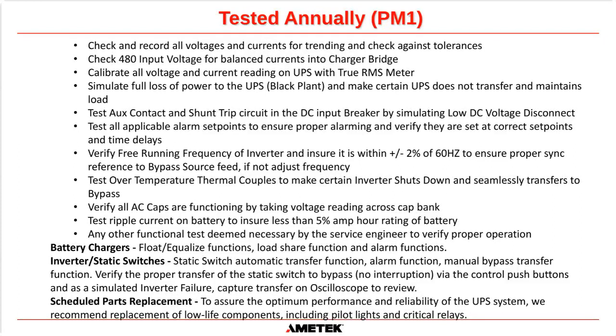We also test the over temperature thermocouples to make certain the inverter shuts down and seamlessly transfers to bypass when necessary. They're basically monitors that once you go above 90 degrees C on our heat sinks, then we will cause the inverter to shut down and transfer to bypass. We also have them on chargers and the static switches. Some of them will just alarm, some of them actually have actions that will shut things down, but we test them to make sure that they work.